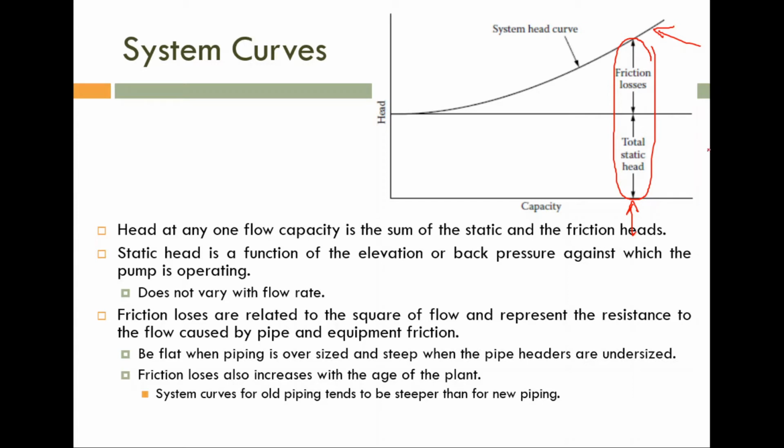Please note, this friction loss will be more if you are pumping a viscous liquid. Because if you are pumping viscous liquid, the friction due to that liquid is high, so definitely the friction loss will increase. So what we are transporting is also very important. Even temperature is an important one, but here we are assuming that the temperature is constant. So we need to know the system curve before selecting the pump. We also have to know the required efficiency.